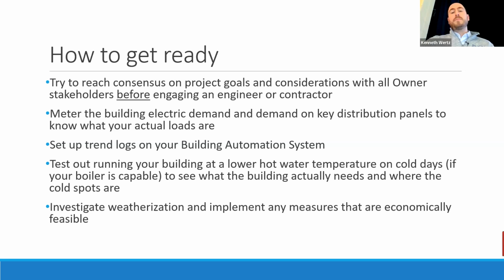With respect to the ability of heat pumps to maintain higher or lower hot water temperatures, again, we can do the calculations and tell you what we think would work, but there's nothing better than having hard data. So if you have a boiler that can handle it and can do a reset down to a lower temperature, it could be worth trying it out for a couple hours on a cold day.